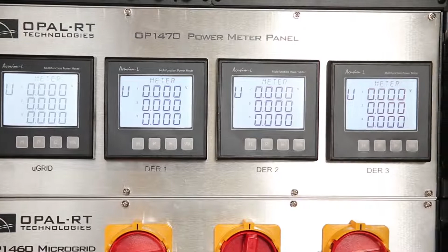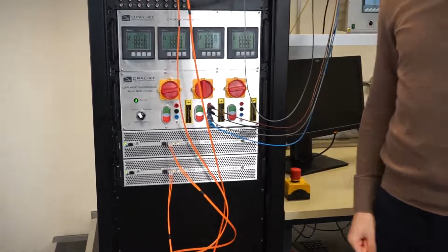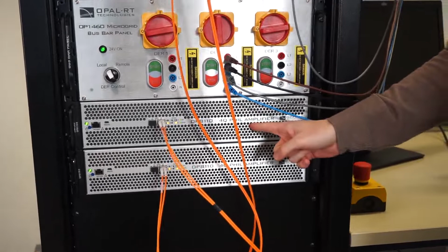Let's switch to the heart of this test bench, the OP8110 4-quadrant power hardware-in-the-loop amplifier. This one is composed of 2 groups of 3-phase amplifiers, while this one is composed of 1 group of 3-phase. Each group has 5 kilowatts, and it can be operated in AC mode, DC mode, voltage mode, and current mode as well. In terms of performance, innovative technology based on soft switching cells with silicon carbide transistors is used, which allows to have no dissipation and an energy efficiency higher than 96%.